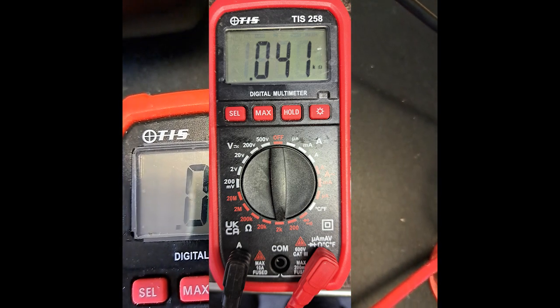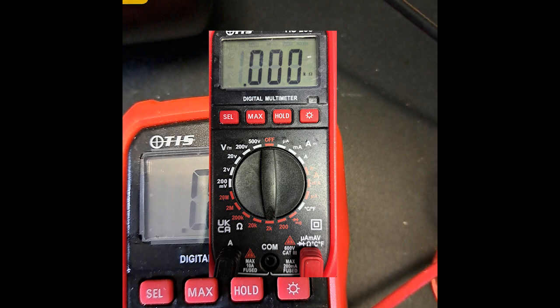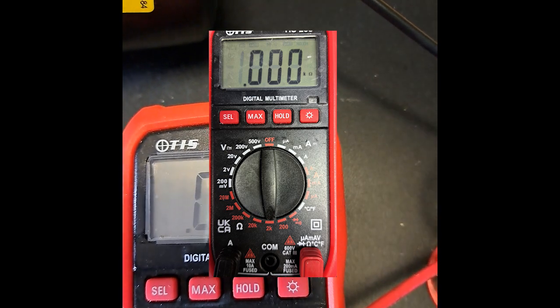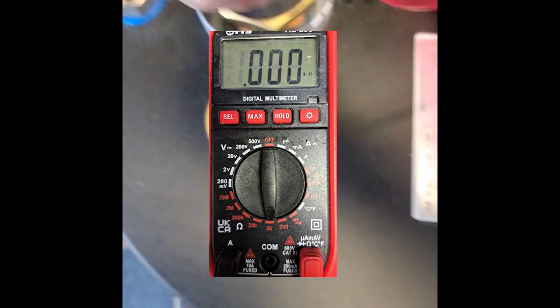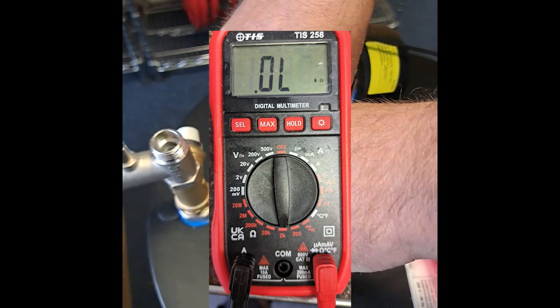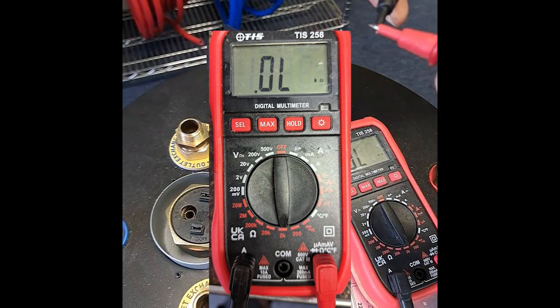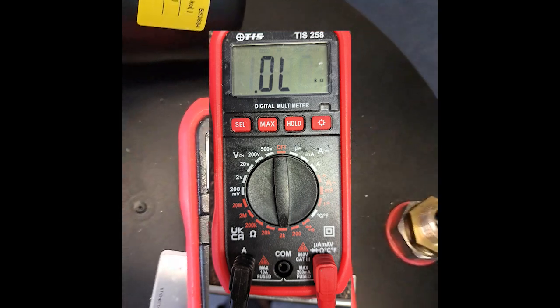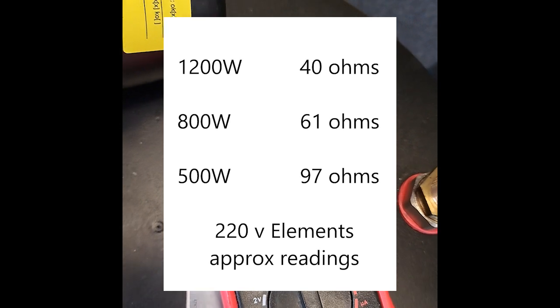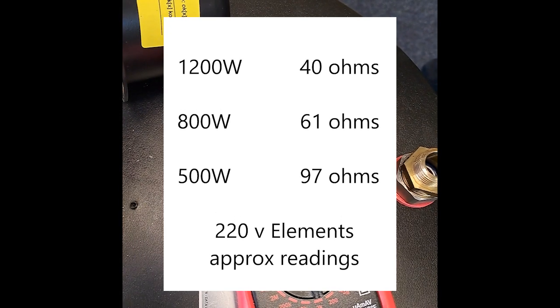If the reading shows a dead short, then the element is burnt out and will need to be replaced. If the reading shows an open circuit, this also tells you that the element needs to be replaced. Here you have a simple chart telling you the correct resistance in ohms for all the elements that we supply.